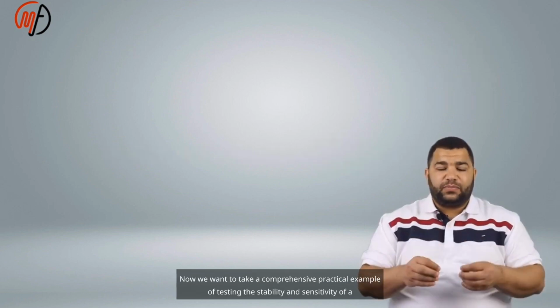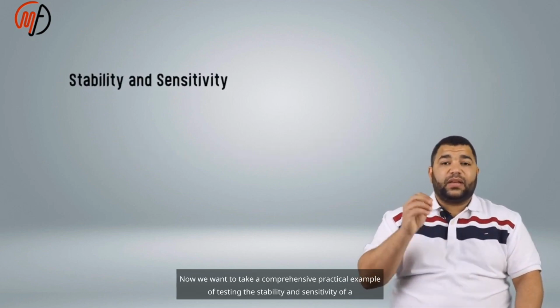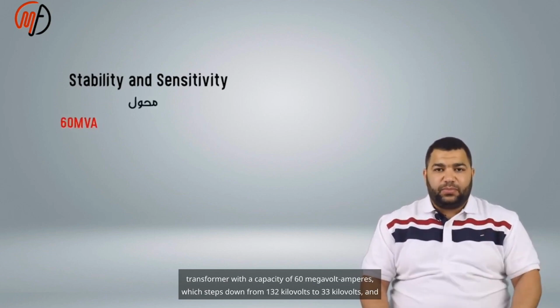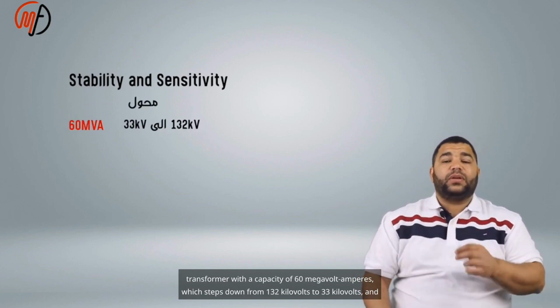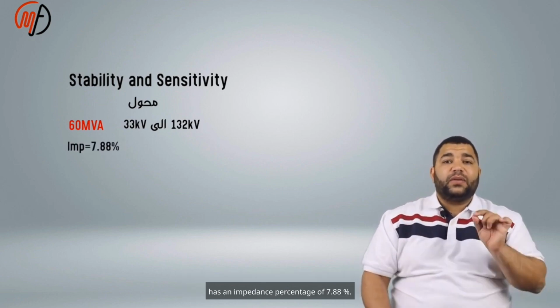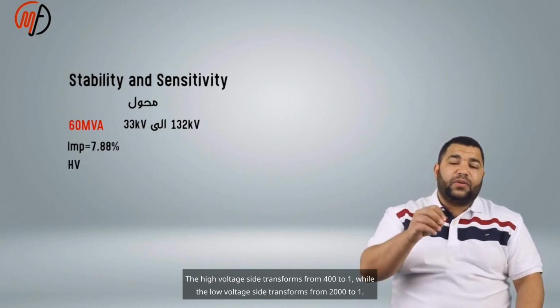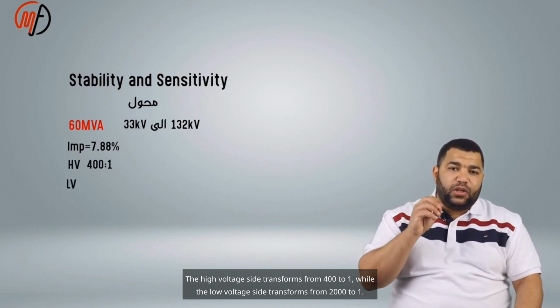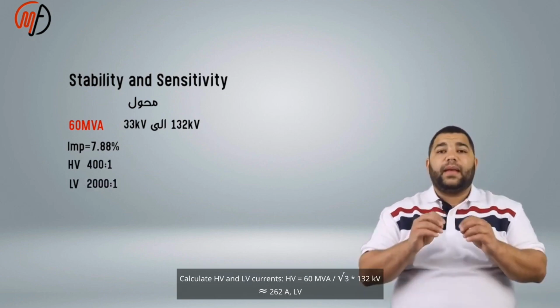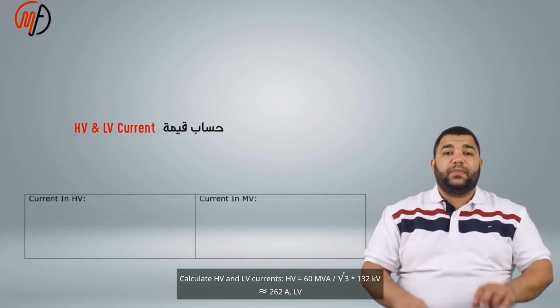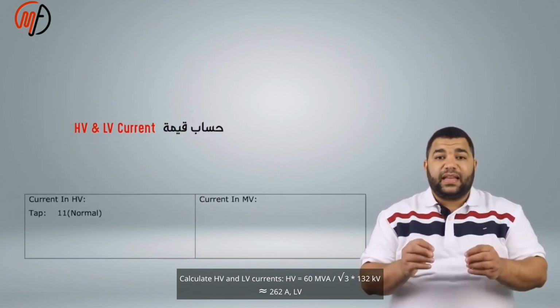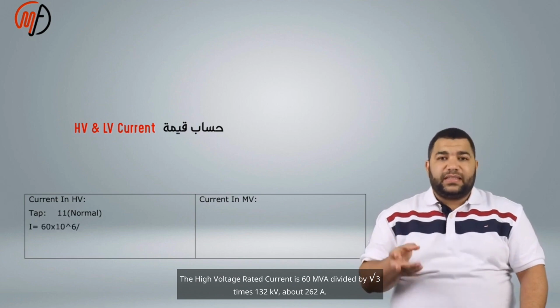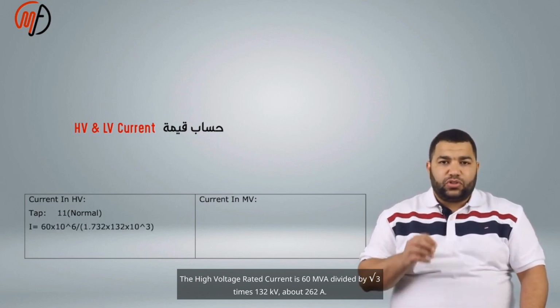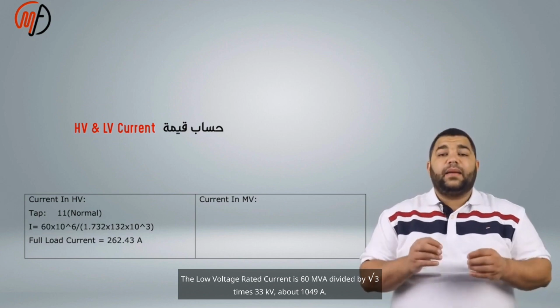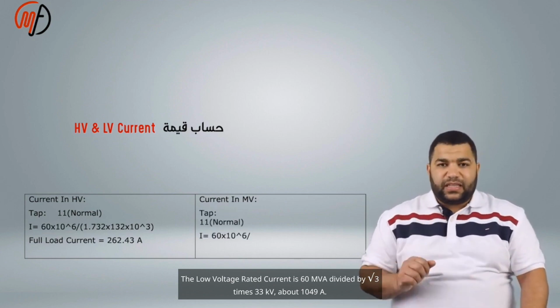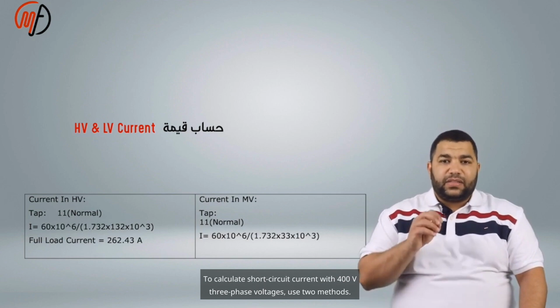Now we want to take a comprehensive practical example of testing the stability and sensitivity of a transformer with a capacity of 60 megavolt amperes, which steps down from 132 kilovolts to 33 kilovolts and has an impedance percentage of 7.88%. The high voltage side transforms from 400 to 1, while the low voltage side transforms from 2000 to 1. Calculate HV and LV currents. The high voltage rated current is 60 MVA divided by root 3 times 132 kV, about 262 A. The low voltage rated current is 60 MVA divided by root 3 times 33 kV, about 1049 A.